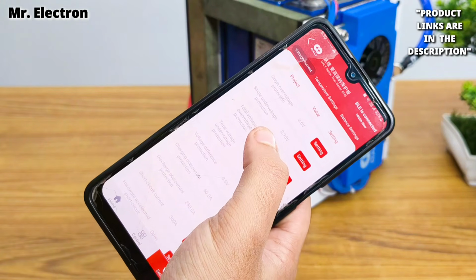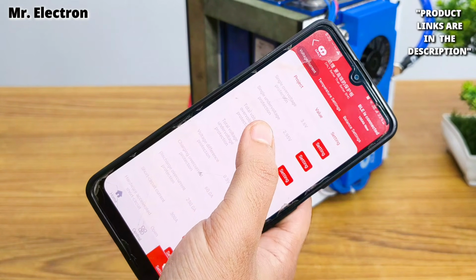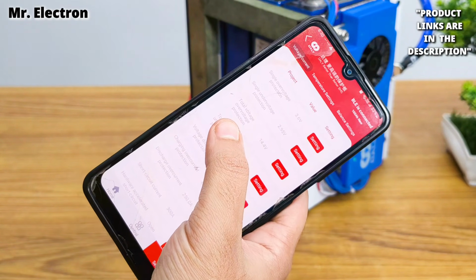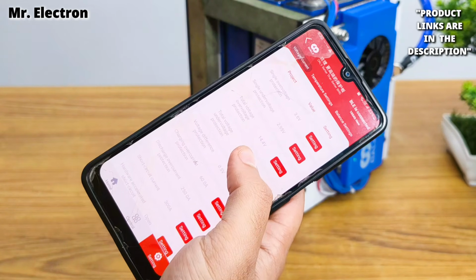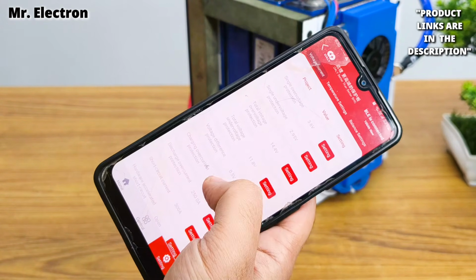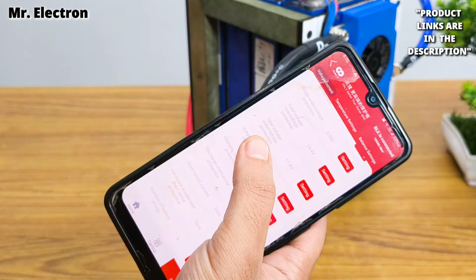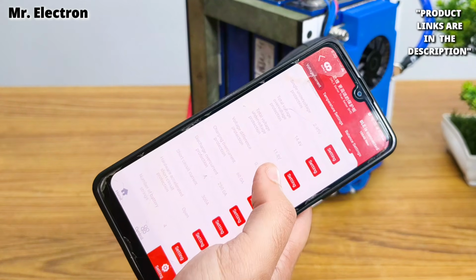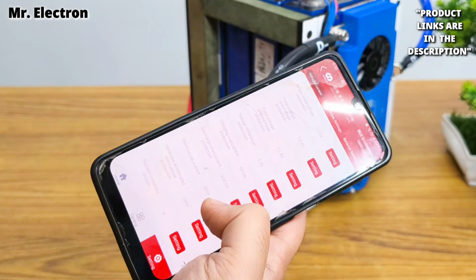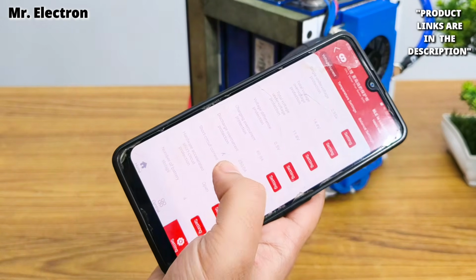Single cell under voltage protection is 2.95 volts. Total voltage over voltage protection is 14.4 volts maximum. Total voltage under voltage protection is 11.8 volts, and so on. Charging over current protection is 60 amps, and discharge over current protection is 250 amps, because my BMS is rated 250 amps.